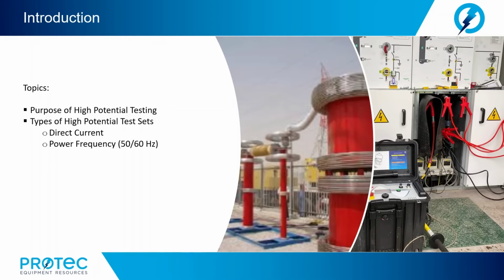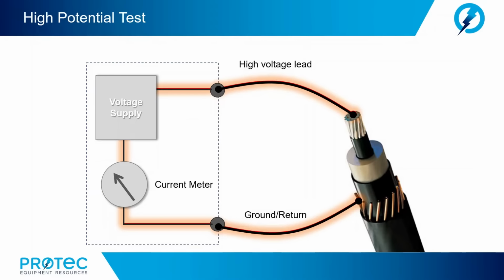A high potential test may be done as a factory test on new equipment, or it may be done on apparatus already in service as part of a routine maintenance test. Now, voltage withstand testing is done with a high voltage source and voltage and current meters. A single instrument called a high pot, or sometimes referred to as a dielectric test set, is often used to perform this test. It applies the necessary voltage to a device and monitors leakage current. The current can trip a fault indicator, and the tester has output overload protection.